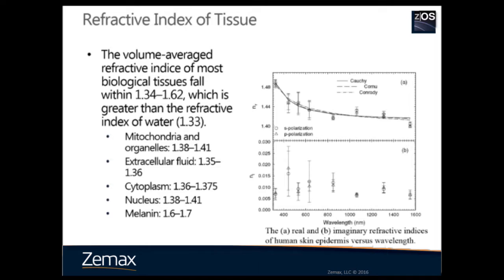Tissue is part of the optical system, so we need to know its refractive index when we design an optical system. Typically we use 1.33, similar to the refractive index of water. However, as you can see from this slide, the refractive index varies a lot from tissue to tissue. For example, a nucleus is about 1.4 and melanin is about 1.6. Also, as shown in this figure, the refractive index is also a function of wavelength.